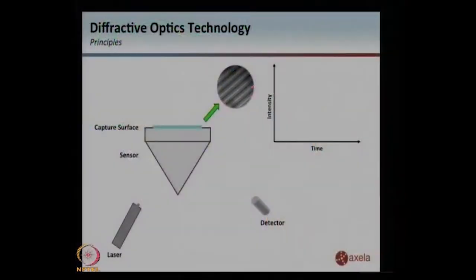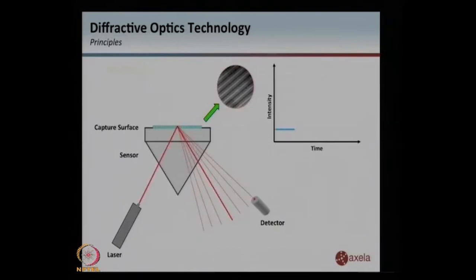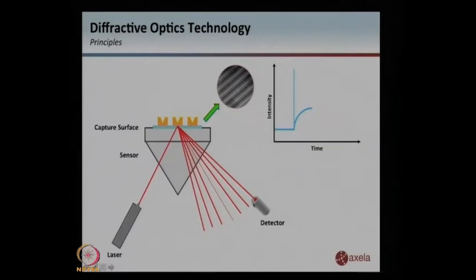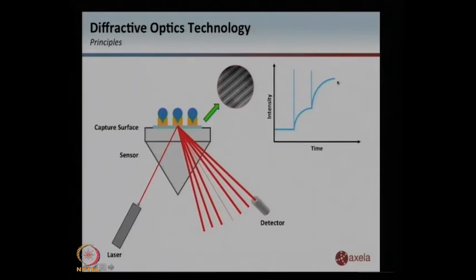The sensor surface is a piece of glass that has lines, as you can see in this inset, and when light is shined through it, there's a very faint signal. Supposing molecules bind right on this line, the signal gets darker, represented on the right-hand side by the intensity of light. If you have a detector in one location, the signal increases with time as binding takes place. If a second molecule binds to the first one, the signal gets darker again. We're thinking multiplexing is possible — you can imagine an antigen, an antibody, and a secondary anti-antibody. You can also play games measuring relative strengths of interaction — if binding is stronger, it may detach a previous molecule, indicated by a decrease in signal.